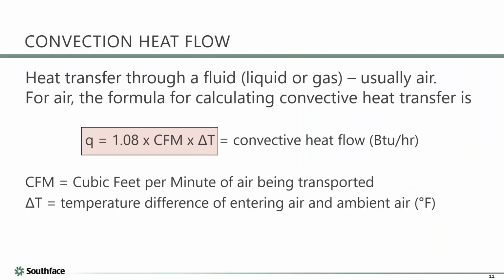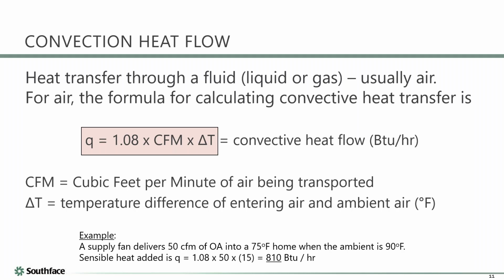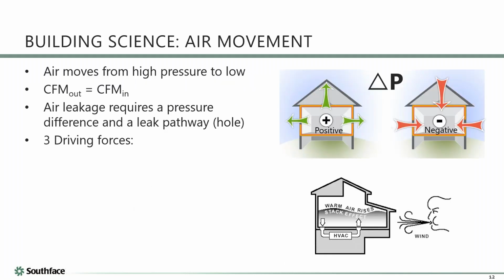Also, this is the equation that I think I forgot to put in our heat transfer one. It's actually a fairly simple calculation. If you've got a certain amount of airflow and the air coming in is cooler or hotter than the air that's in the space it's being delivered to, you can calculate the BTUs per hour that's being delivered. So I had an example. Let's see if it shows up here. So if you've got a fan that's pushing 50 CFM of outside air into a home and the home's being kept at 75 and it's 90 degrees outside, what's the impact on the load of the house because of essentially delivering air that's 15 degrees hotter? So you can plug it into the calculation and you can see it's about 800 BTUs an hour. Okay, that was enough nerd calculation.